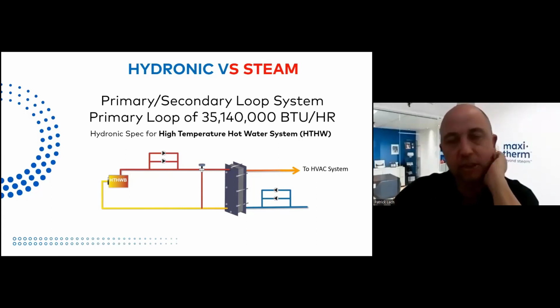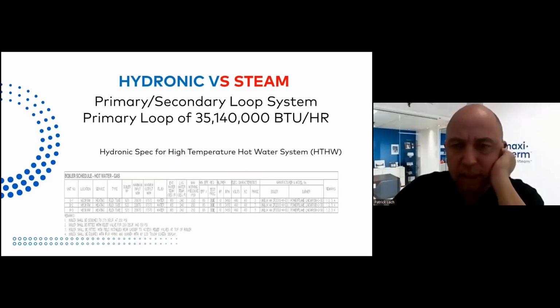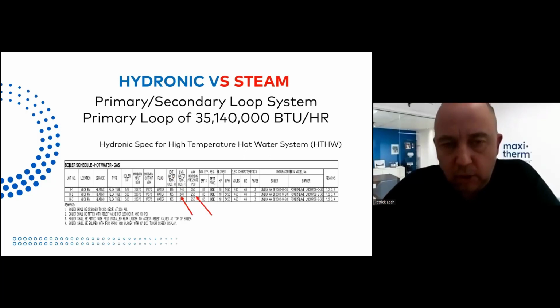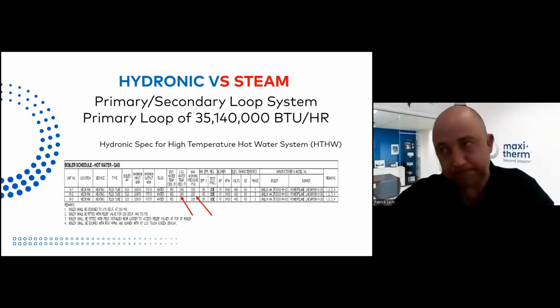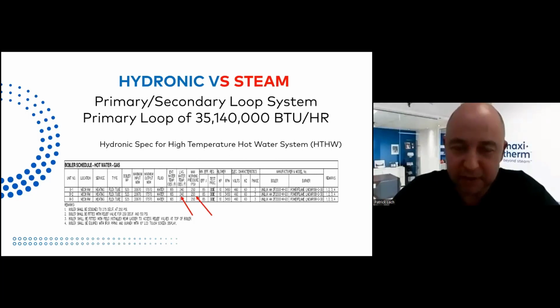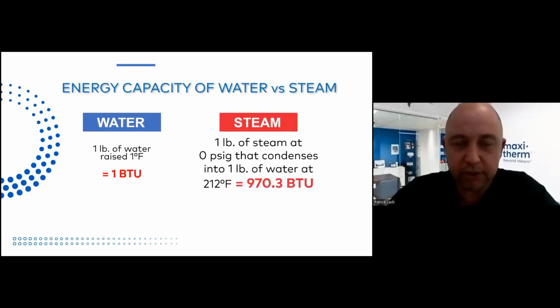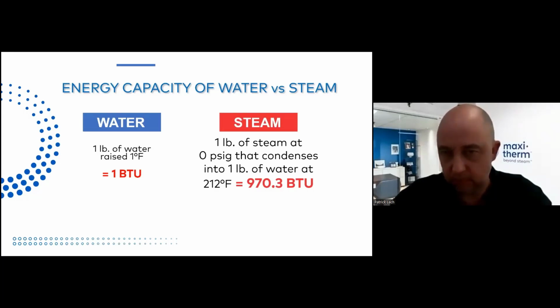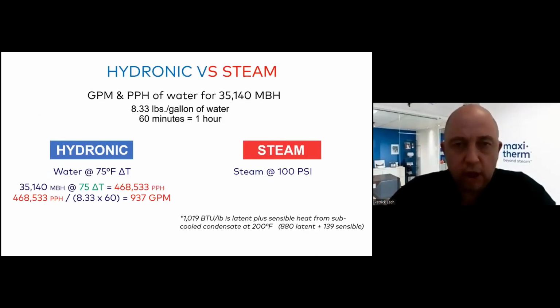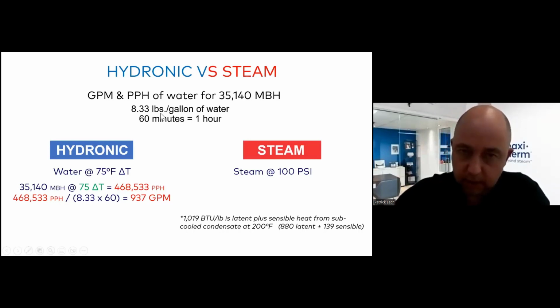Let's do some comparison. So the design specified a high temperature hot water loop at 240 Fahrenheit, 250 psi. That's big, 250 psi hot water. So as a reminder, 1 pound of water raised 1 Fahrenheit needs 1 BTU. One pound of steam that turns into 1 pound of condensate gives you about 1,000 BTU, right? And that's conventional design. Okay, so the hydronic loop for a 35 million BTU total load was specified. Okay, these are again reminders: there's 8.33 pounds per gallon of water, 60 minutes per hour, right?